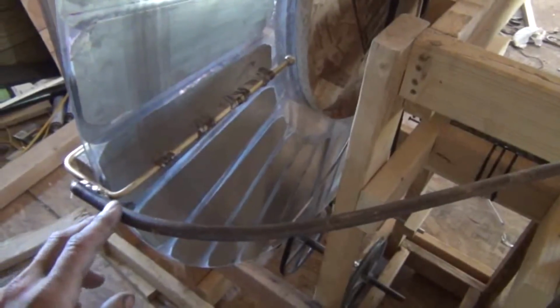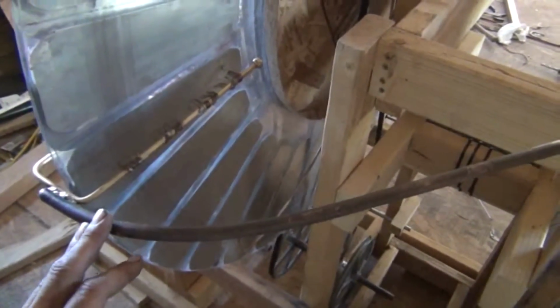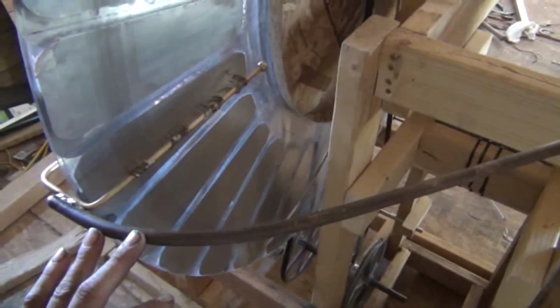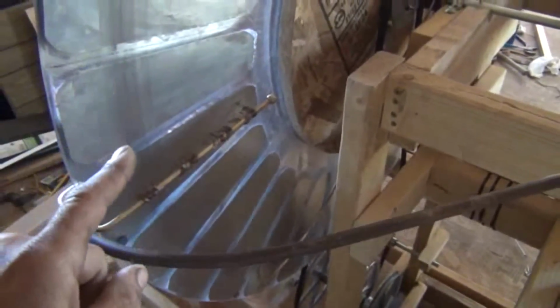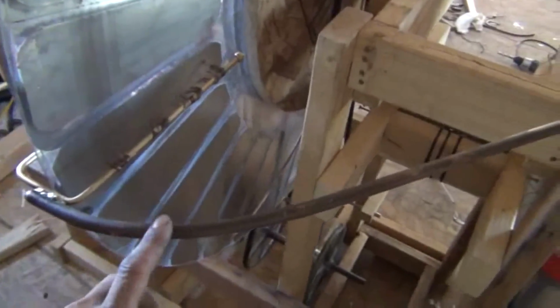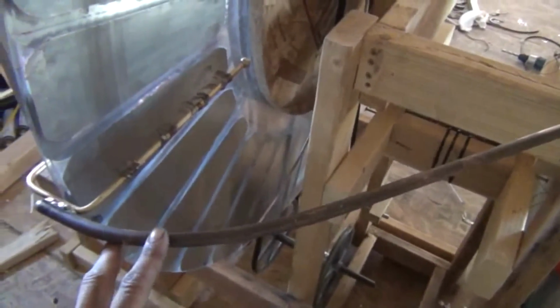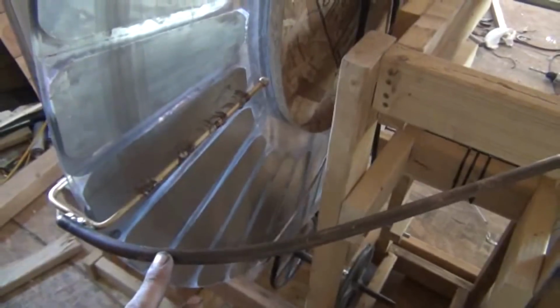Now this is 5/8 inch rod. The problem is that 5/8 isn't high enough to carry the actual voltage on the surface, the skin effect basically, that's being generated by this generator. So I may have to go to, let's say, a 3/4 or a 1-inch rod right here to give me enough surface area to carry the charge I'm looking for.